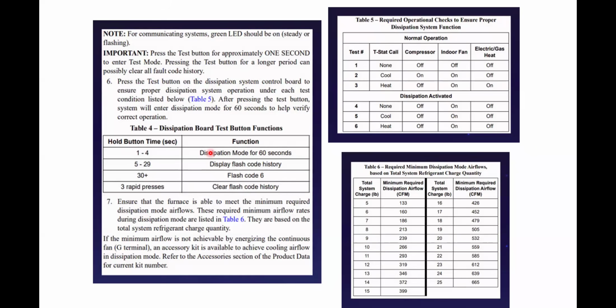Because what they did is they took the thermostat wire and they went right to the furnace with it. Whereas the thermostat wire needs to go into the leak board and then to the furnace. All they did is wire the thermostat to the furnace, and then they wired the leak board to the furnace, and then the thermostat had a way to turn everything on without going to the leak board, and hence it was useless.